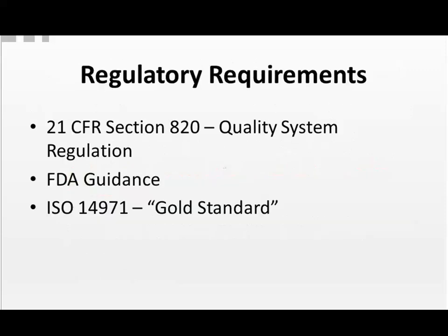Now, in terms of the regulatory requirements as they relate to risk analysis, there are basically three groups of regulatory documents here in the U.S. 21 CFR 820, the Quality System Regulation, which indicates that risk analysis be performed as part of medical device regulatory submissions, with risk analysis being required as part of design validation. FDA guidance: there are at least two guidance documents that apply, incorporating human factors into risk management and pre-marketing risk assessment. And finally, there's ISO 14971, the 2007 version, which is considered the gold standard.